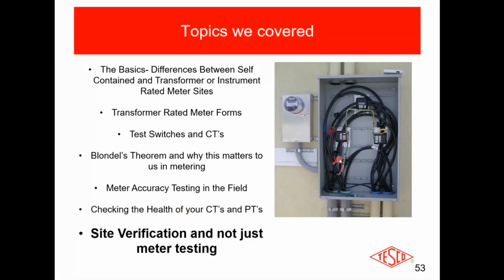So again, why is it hard to see whether these transformers are all in the right direction? Yeah, you bet. It can be a little daunting to figure out, is this one the same? Yeah, okay, it's going this way, and then that one's going this way, and that one's going that way. Is that all the right direction? And the answer is, in this case, yes, but you've got to track it and make sure it is. So the most important thing, if you get nothing else out of it, is site verification. It's not just meter testing. It's not just transformer testing. It's a site test. It's a site verification.